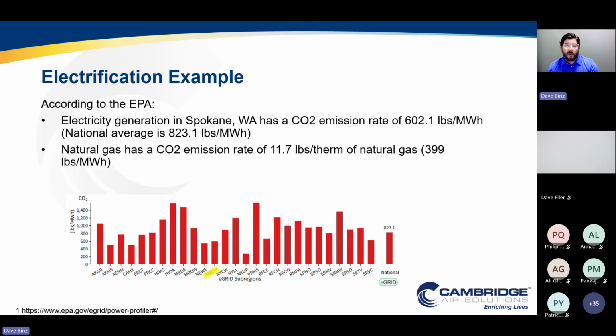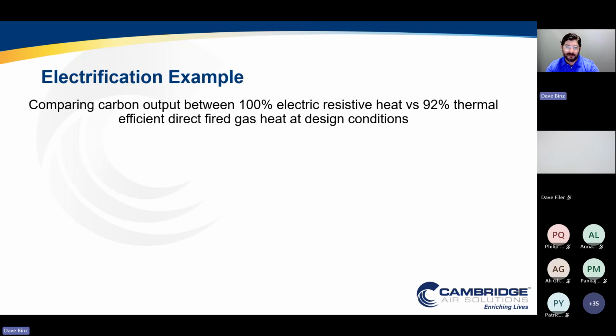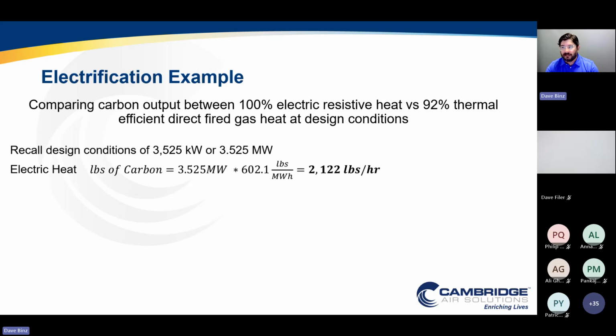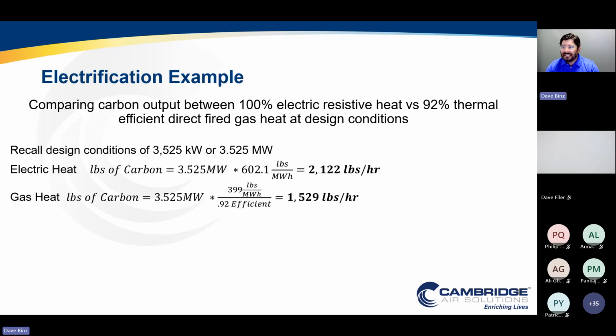So pretty clean power. However, here's what natural gas, when we look at space heating, has: a very low CO2 emission, only about 400 pounds per megawatt. So about half of the national average, and about 2/3 of what the electric grid would look like inside of this facility. So again, the goal for this customer was improve ventilation, improve thermal comfort, and reduce greenhouse gases. And what we did is analyze, if I use natural gas versus electric heat, what actually are the CO2 emissions? This was using electric resistance heat.